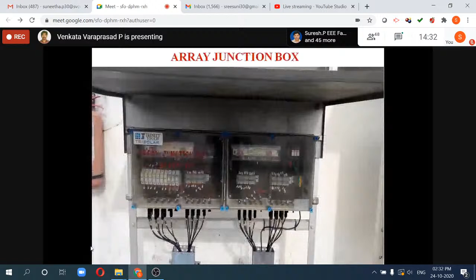And those strings are connected to the array junction box. So here in the down point, you can see the strings and the cables. These are nothing but string cables. Here I can see nearly 7 cables, 7 strings, in that particular block. The positive string cables are connected to a fuse point for protecting purposes. We require a fuse, and this fuse is connected to a bus bar. Here you can see the bus bar at the top point. From this bus bar, another positive connection is given to the inverter. I will show you later.